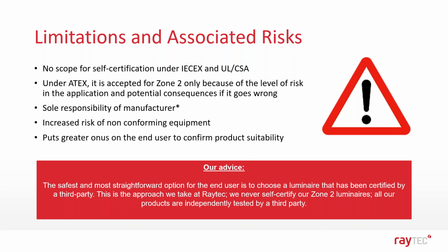So a manufacturer can choose to self-assess their products against the requirements of the relevant standards, and in those situations would be solely responsible for the safety assessment of the product. Now, obviously, with this approach comes an increased risk of non-conforming products being placed on the market. And in these situations, there is a greater onus and element of risk on the part of the distributor and the end user to confirm the suitability of the product for the application.